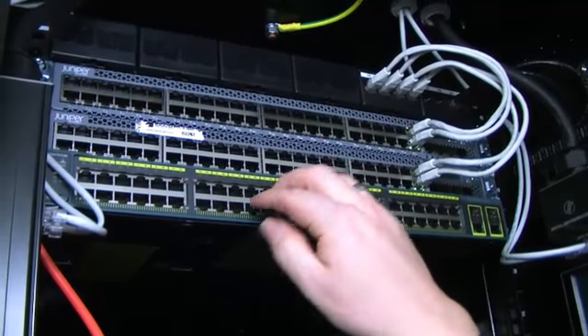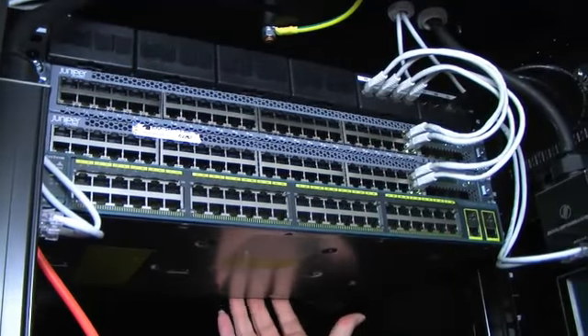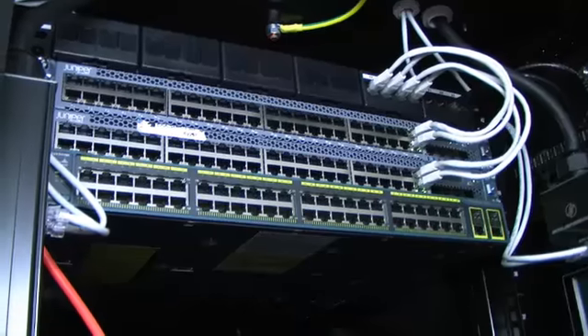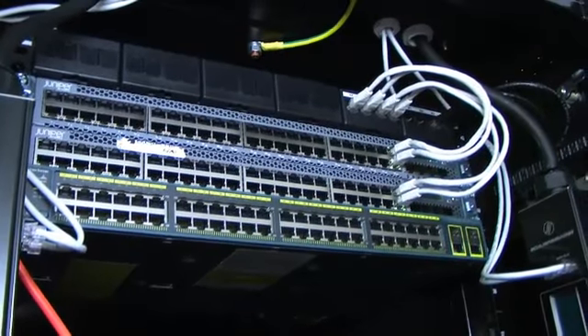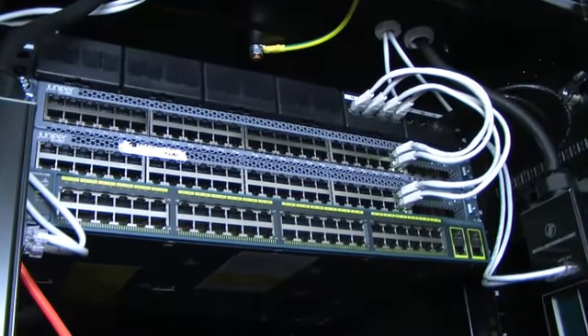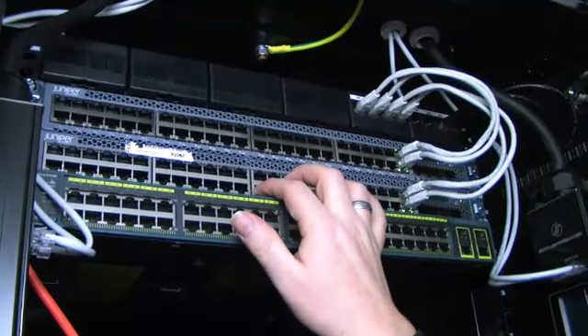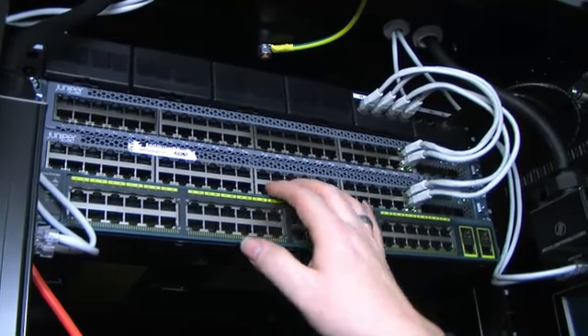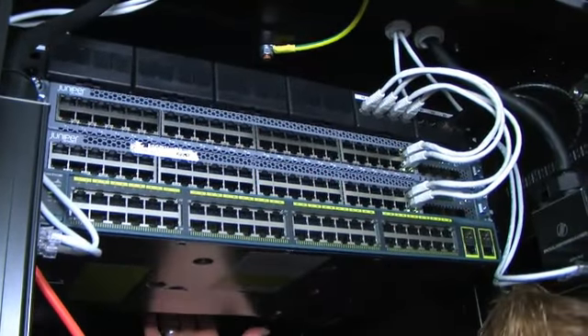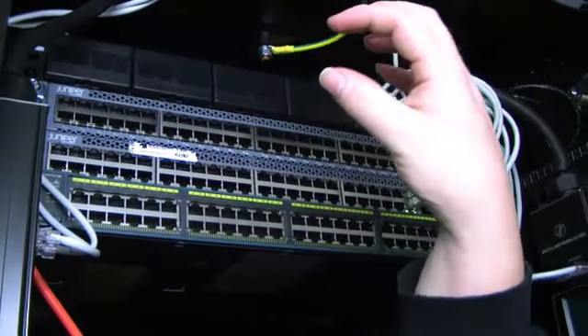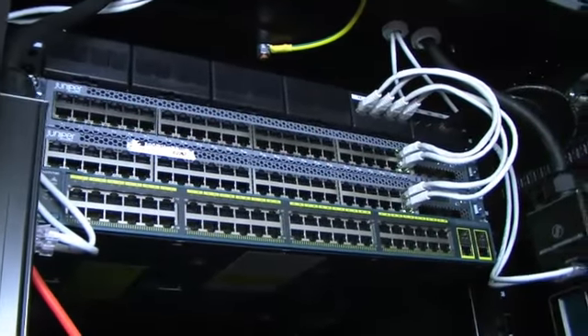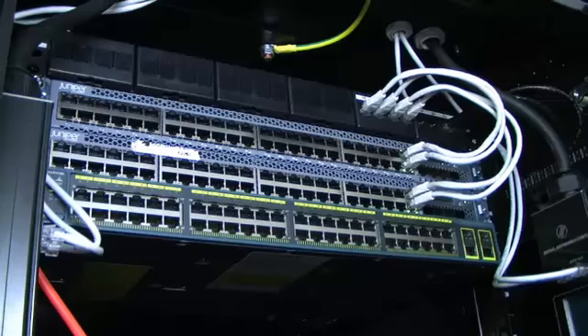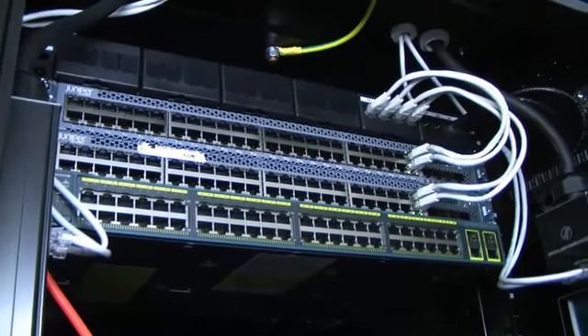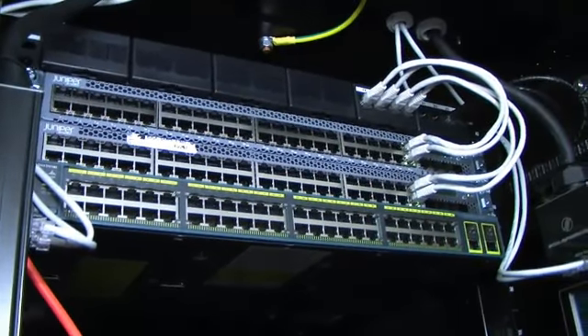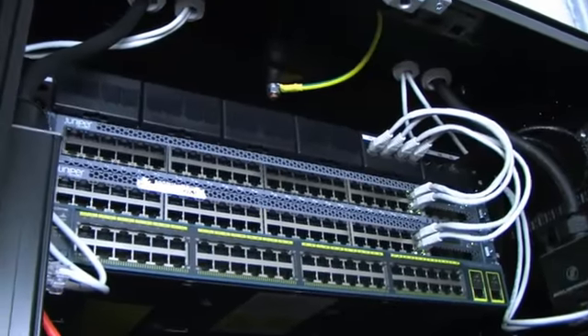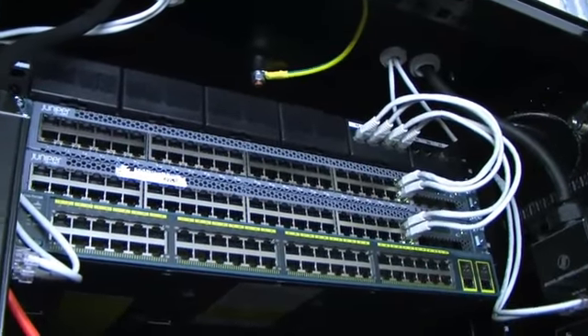typically a switch heats from front to back, and because of the nature of this data center, the hot aisles are going to be quite warm. When we ordered those from Juniper, we had them back to front, so the cooling comes in the back and the hot air comes out the front. So they're the opposite way around of a typical switch. Because you want access to the switches in the hot aisle. You want the front of the switch to be in the hot aisle. Exactly. We call those TOR. They're top of rack switches.